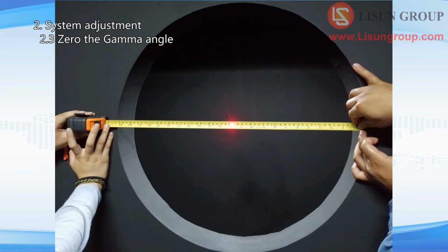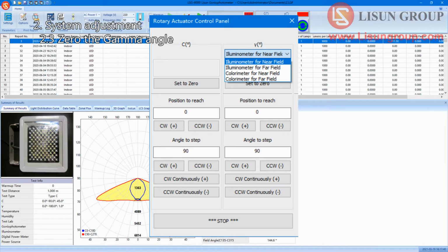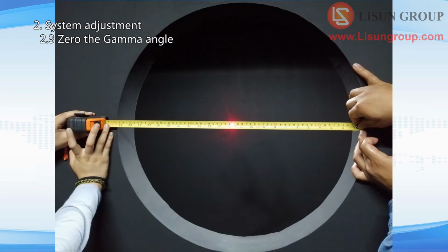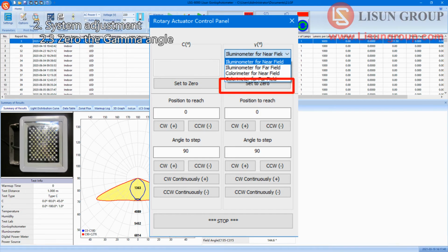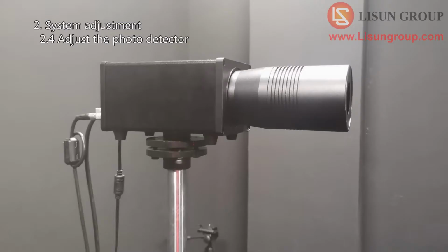The laser should go through the center of the hole of the partition. If you have more than one partition in your darkroom, just refer to the last one. If the laser is not in the center, please input a small number and choose a direction to rotate according to the actual situation. Make sure the laser goes through the center of the hole. Then this is the real 0 degree position of the photodetector. Click Set to 0. The password is Lisun Group. It displays 0 at gamma angle after setting 0 successfully.